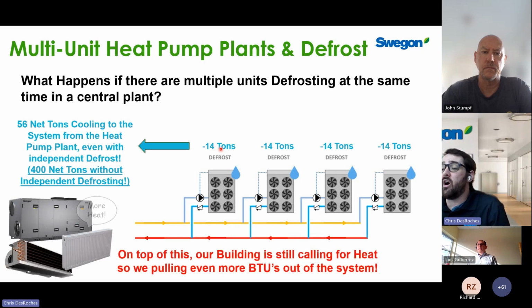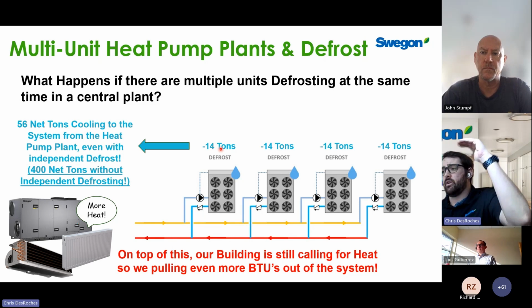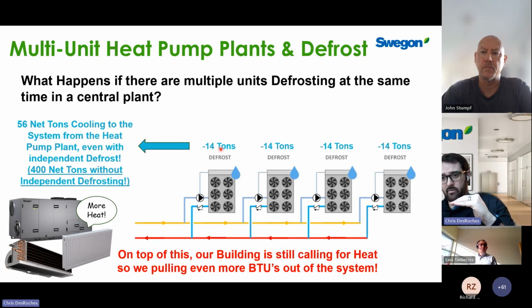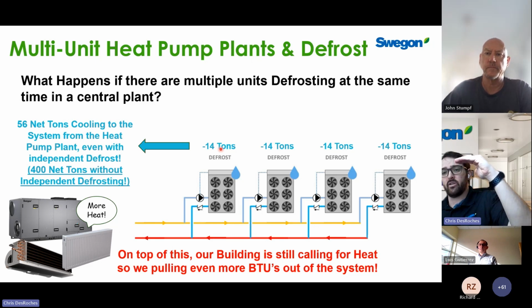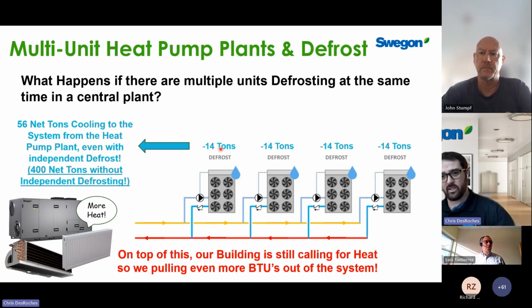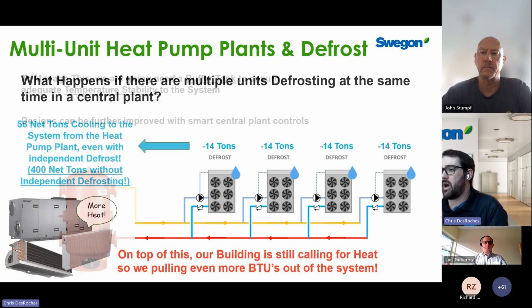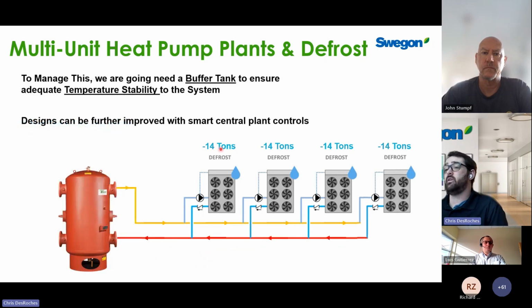But what a lot of designers don't think about as well is we need to think of the heat load on the plant as well, because our air handling units or fan coil units, they don't care if the heat pumps are in defrost. They have valves that are opening asking for more water. So we need to consider that heat load as well, because if you undersize your volume too much with these heat pumps, when you go and defrost, your supply temperature will drop off. You try to heat the water back up in the system over time, you're still pulling heat, so it takes longer to react. And then after an hour, we might have increased the temperature by 10 degrees and, oh, we got to defrost again, right? So it's kind of one step forward, 2 steps back. So this is why system water volume is going to be very, very important.